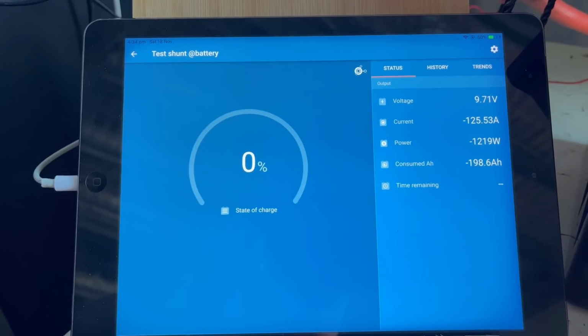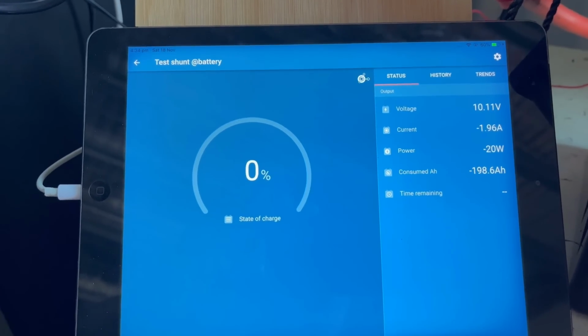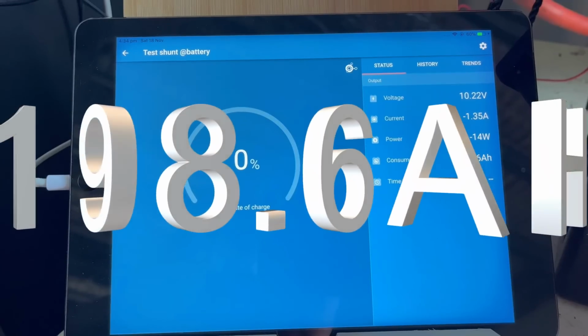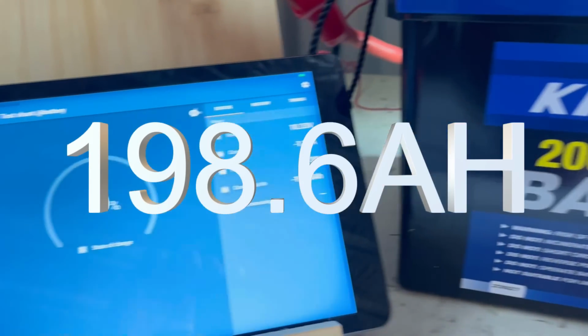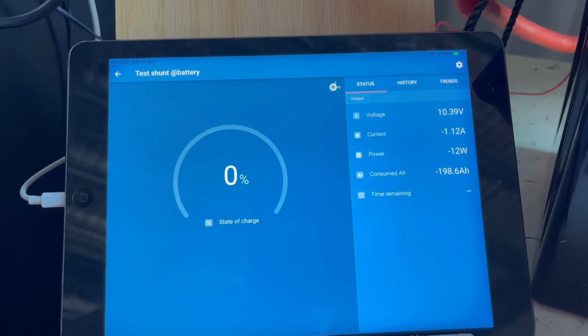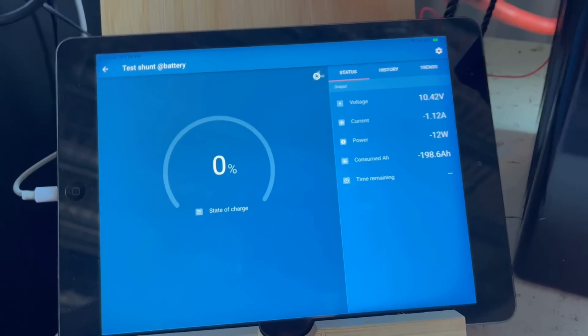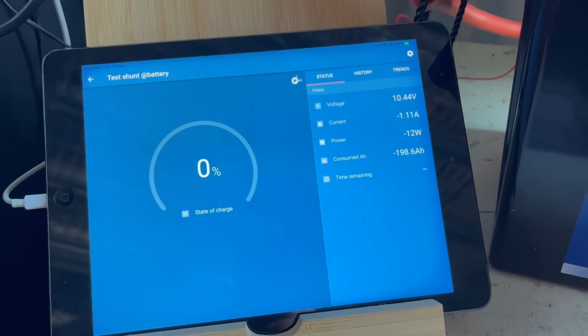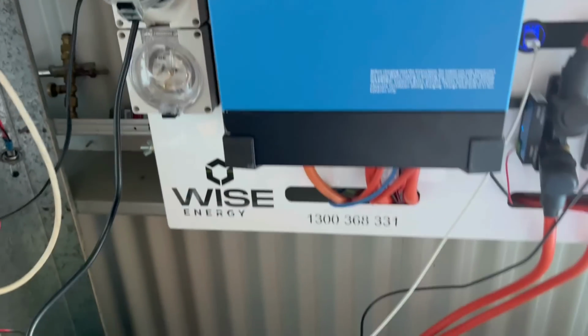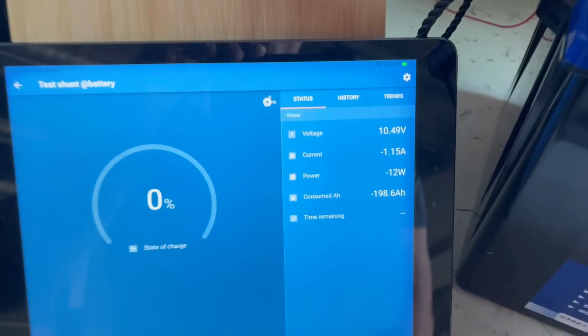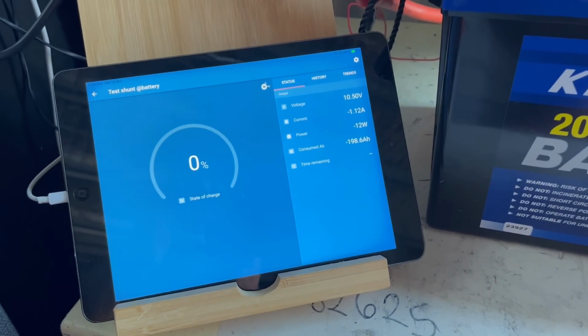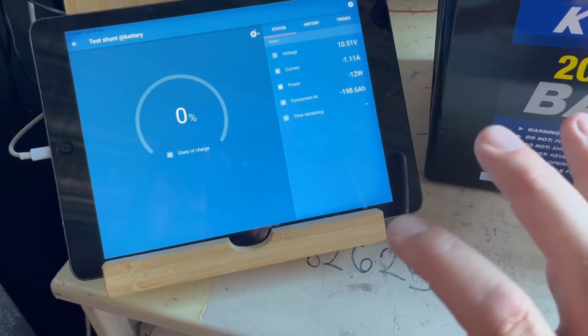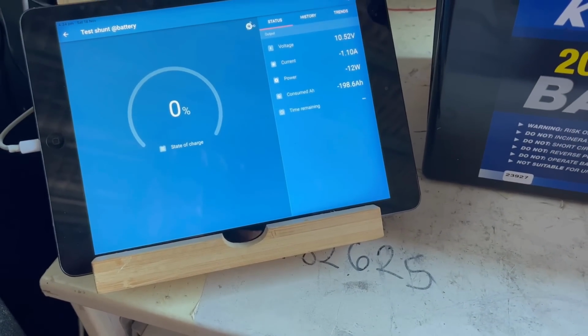Again, that's at the, and it's just cut out, low battery, and we got 198.6 amp hours out of this rated 200 amp hour battery. Am I going to complain at 1.4 amp hours? I don't think so. And you know what, I could put my little light globe on there and probably pull the extra 2 amp hours out of it. So it's low battery on the Multiplus, so I'd say the Multiplus tripped before the BMS. I'm going to call that a pass on the discharge test. I don't really have a problem, I'm not going to debate 1.4 amp hours.